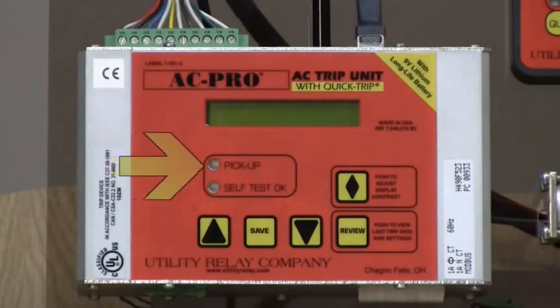The red pickup LED is on whenever the current on any phase is greater than the long time pickup setting. The green self-test OK LED indicates that the AC Pro is functioning properly. The AC Pro is continuously doing a self-test and checks the connection to the actuator, the software routines, and the microcontroller. The AC Pro has a 9-volt replaceable long-life lithium battery.